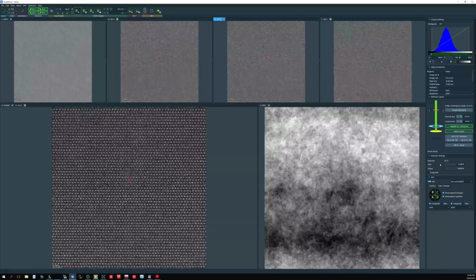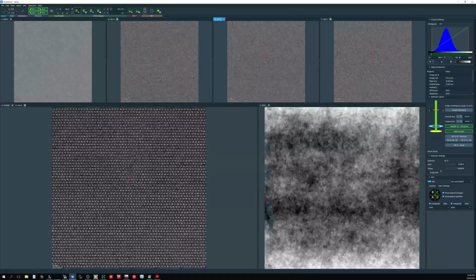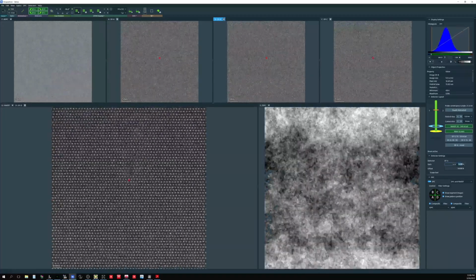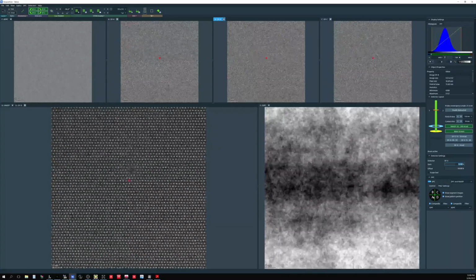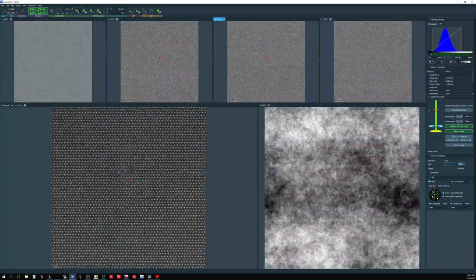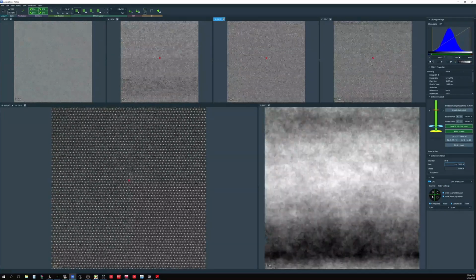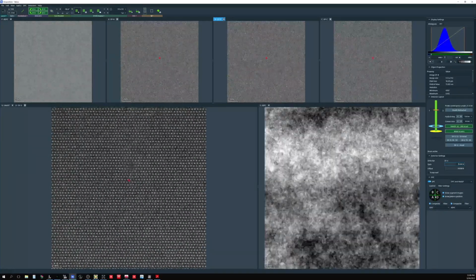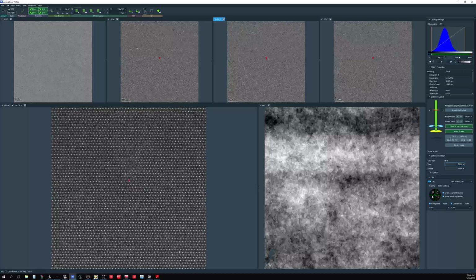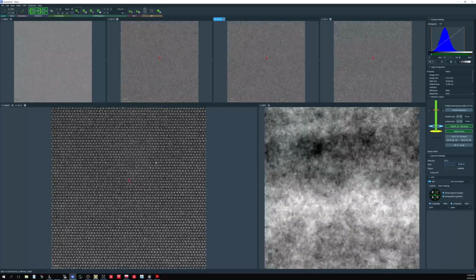So come to here and make sure the offset is set to 100%. You can adjust the gain a little bit and you see the cross moves position just a little bit. So you can fine-tune the gain to make sure that the cross is at the center of the detector. Now we can retract the screen by clicking the R1 button.